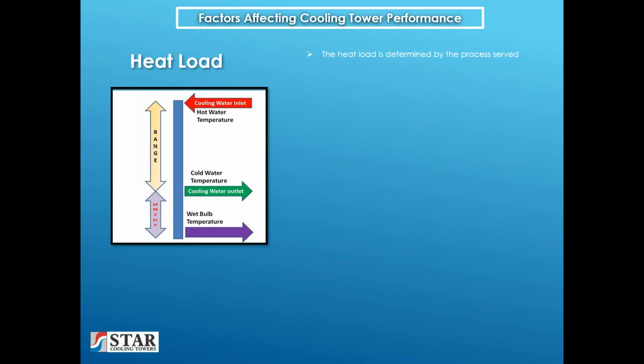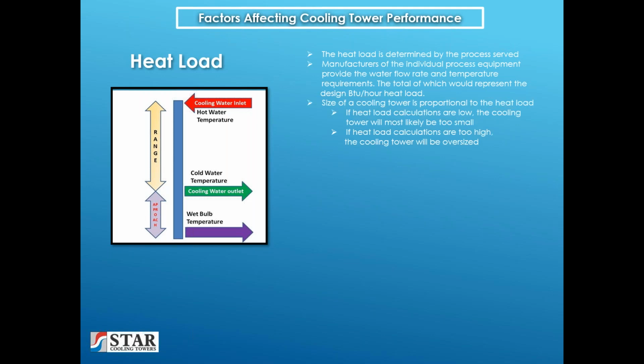So we'll talk about heat load. The heat load is actually determined by the process it serves. Originally, when the tower was first designed, manufacturers of the individual process equipment provided the water flow rate and temperature requirements of each piece of equipment, the total of which would represent the design BTU per hour for the heat load. The size of the cooling tower is proportional to the heat load. If the heat load calculations are low, the cooling tower would most likely be too small. If the heat load calculations are too high, the cooling tower obviously would be oversized.